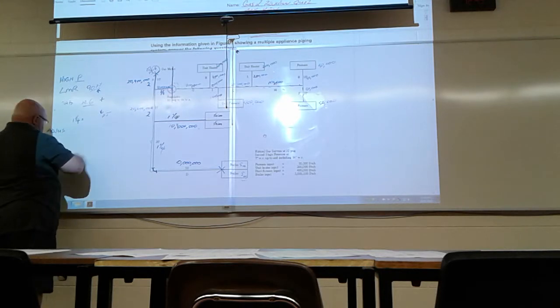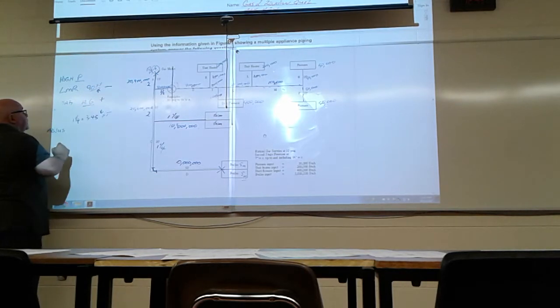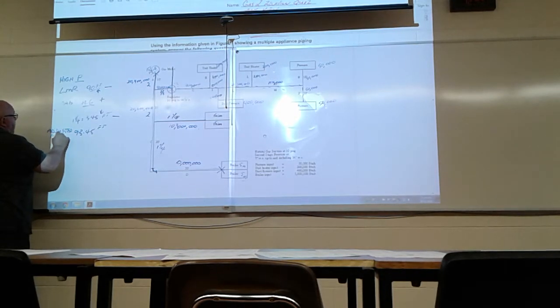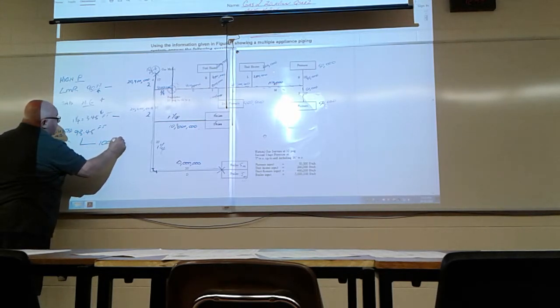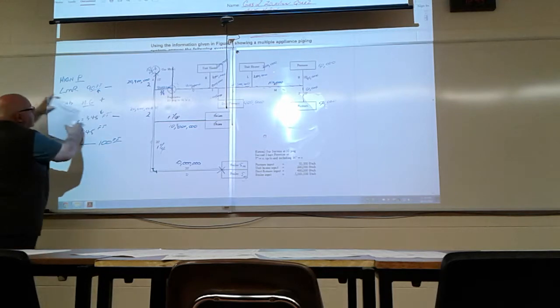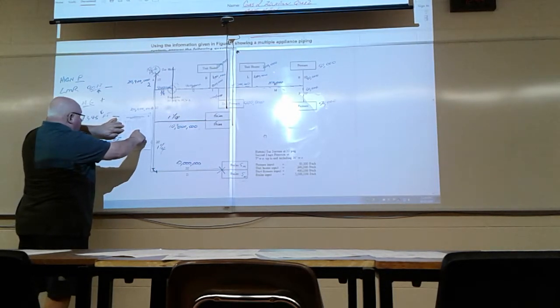Okay, so if I look at Imperial on page 145, it is 3.45. So I add the longest measured run, plus the fitting, and I have 93.45 feet, and that's the new adjusted longest measured run. So I have to do everything all over again based on the 100-foot column for the length of pipe. So now I have to go from the 90 to the 100 to account for that fitting. And if I go across there, you're gonna find that nothing has changed. Okay, everybody good?